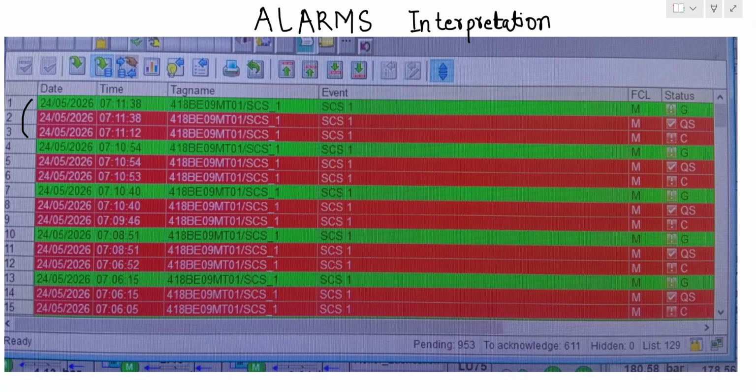The specific alarm in the machine, that of this speed sensor, has appeared at this specific time. If you look at the status, it has been marked as C. Well, it is the incoming alarm. The incoming alarm means that the specific alarm has been triggered at this time. The speed switch of the motor has disappeared. It has gone, it is missing. This is why this alarm is triggered.